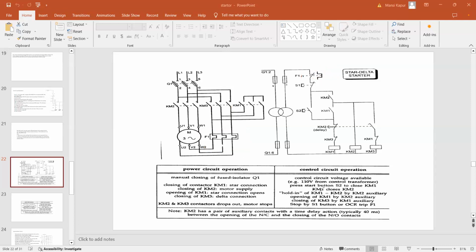So what happened in the control circuit? You are going to reduce the voltage first. For example, with 220 volts, we are reducing to 110 volts from the control transformer. This is your control transformer. Press the start switch S2. To close the KM1, your circuit will get completed from here and KM1 will energize and this KM1 will close. Understood this much?